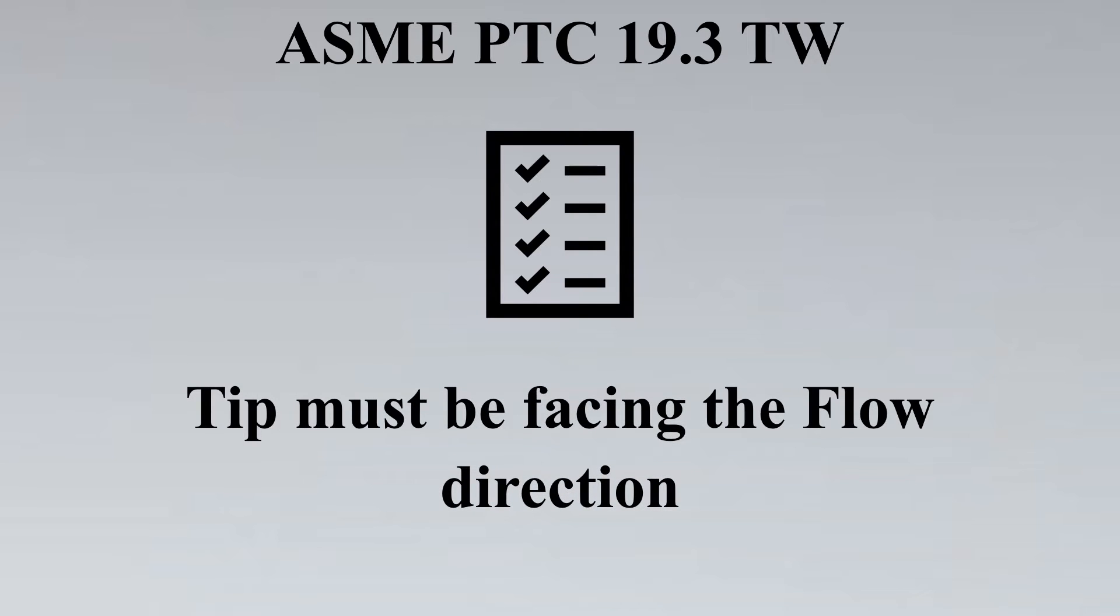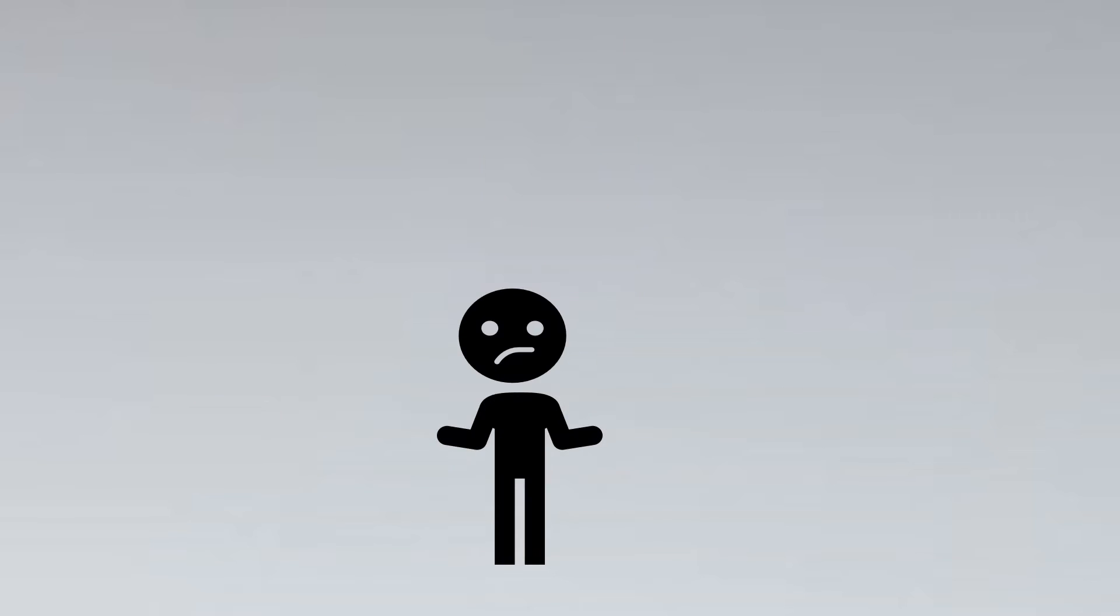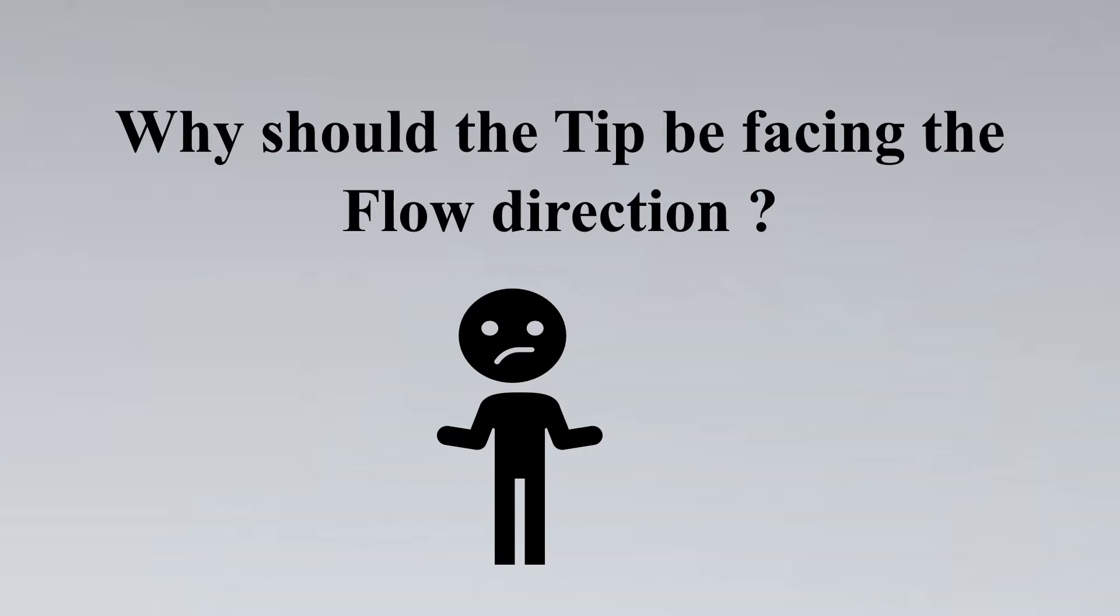What does this standard say? It states that the tip must be facing towards the flow direction. Have you wondered why does it say that? And I think after this explanation, you would also agree with the standard's recommendation that why should the tip be facing the flow direction and not the other way around.